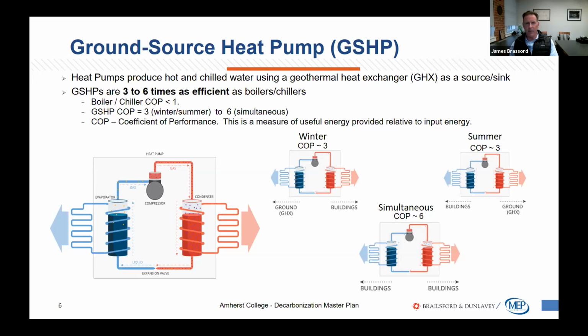Now, the key to this really lies in the fact that it has a coefficient of performance that far exceeds what you'd see from conventional boilers or chillers. Those typically have coefficients of performance of less than 1, whereas a ground source heat pump is typically in excess of 3, either in cooling or heating mode.